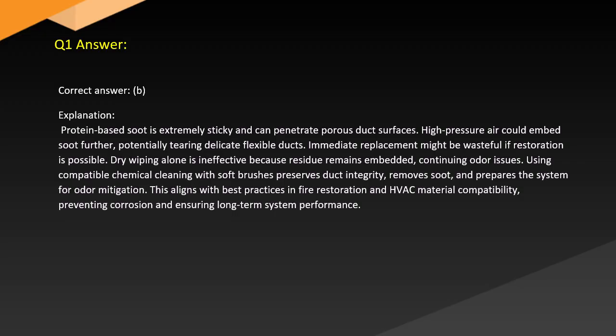Protein-based soot is extremely sticky and can penetrate porous duct surfaces. High-pressure air could embed soot further, potentially tearing delicate flexible ducts. Immediate replacement might be wasteful if restoration is possible. Dry wiping alone is ineffective because residue remains embedded, causing continuing odor issues. Using compatible chemical cleaning with soft brushes preserves duct integrity, removes soot, and prepares the system for odor mitigation. This aligns with best practices in fire restoration and HVAC material compatibility, preventing corrosion and ensuring long-term system performance.